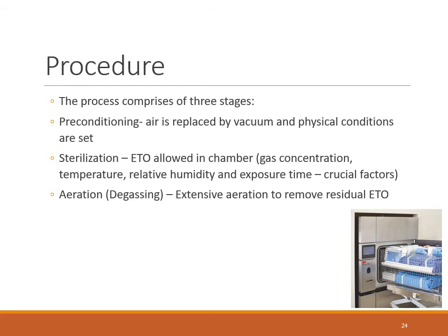And at last the degassing phase, where ETO residues are left on the surgical instruments and tubing that may be toxic to the patient and staff. Therefore, extensive aeration of the sterilized material for 8 to 12 hours is necessary to remove residual gas. We can use it mostly for CSSD. The control will be spores of Bacillus atrophaeus. We can check the process with the help of spores of Bacillus atrophaeus.